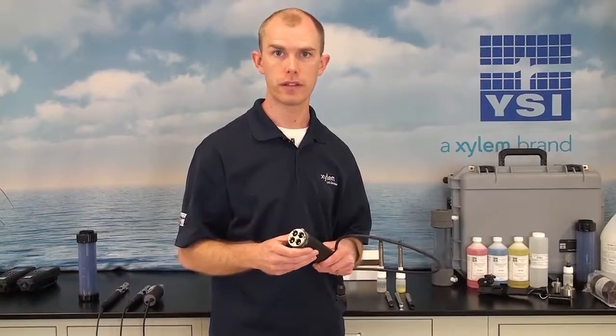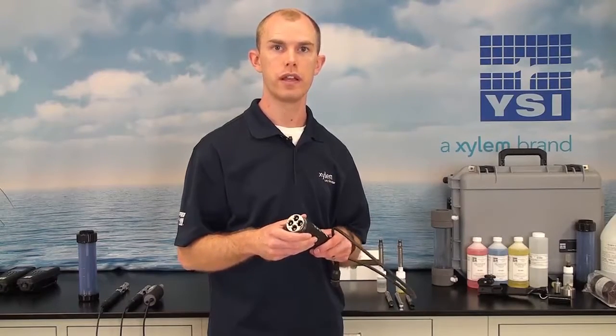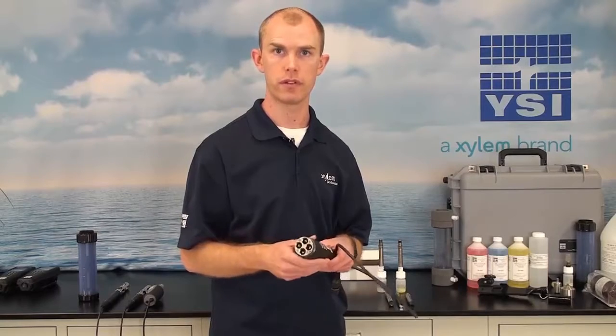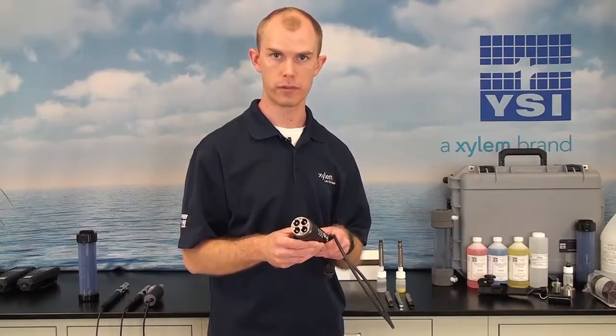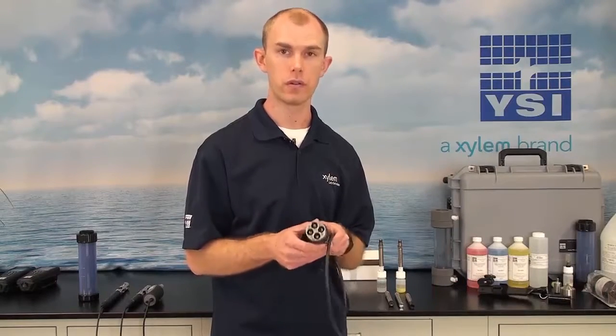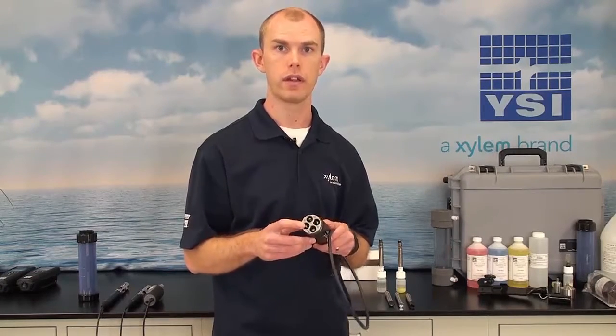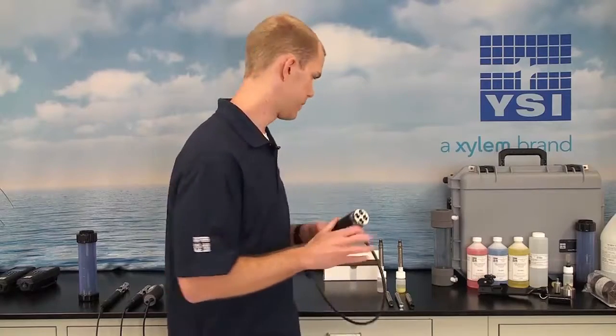The third step in putting together your ProDSS system is to order sensors, if you have a cable with user replaceable sensors, such as the 4-port cable. If you have a cable such as the ProDSS ODO-CT that has integrated or built-in sensors, you don't need to order separate sensors. This step is only for cables that have user replaceable sensors.